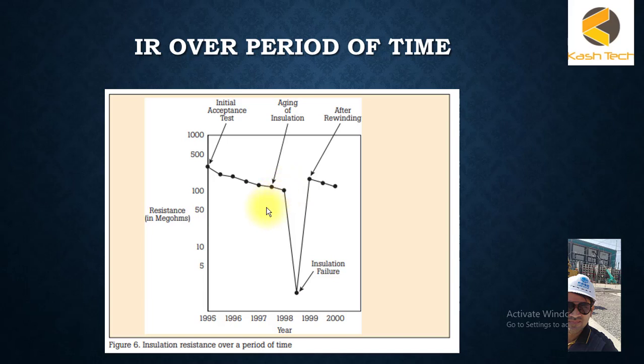But when they tested this insulation here, the value suddenly decreased during this year. When they took the measurements, it showed that insulation has failed or will fail. The value goes down. Normally, the supplier provides acceptable ranges of insulation. For example, if the acceptable insulation range is one gigaohm...